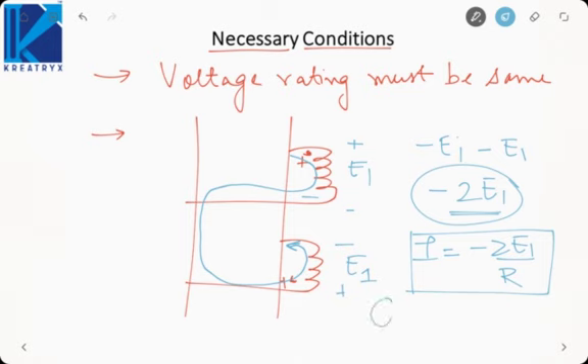This current is called circulating current because it is circulating between the two transformers. This sort of current is always undesirable. Even if we are studying the parallel operation of transformers or generators or motors, any circulating current is undesirable because we want the loads to absorb the power. We do not want one load to deliver power to the other load. Similarly, we want transformers to transform the power, not transfer the power between them two. In this case, one transformer will be delivering power to the other transformer. But we do not want that.